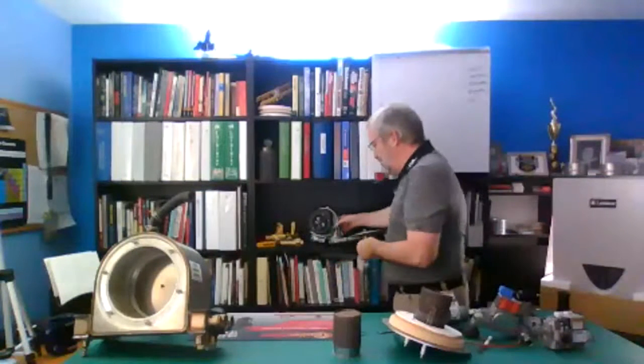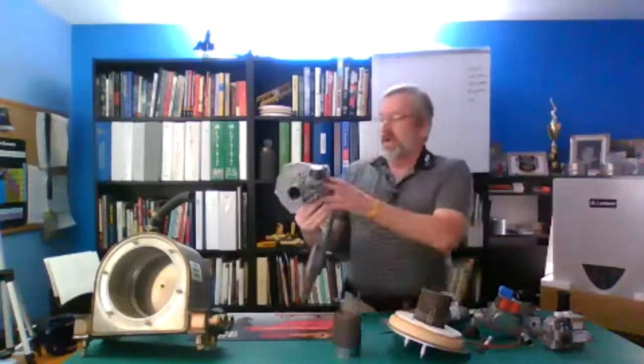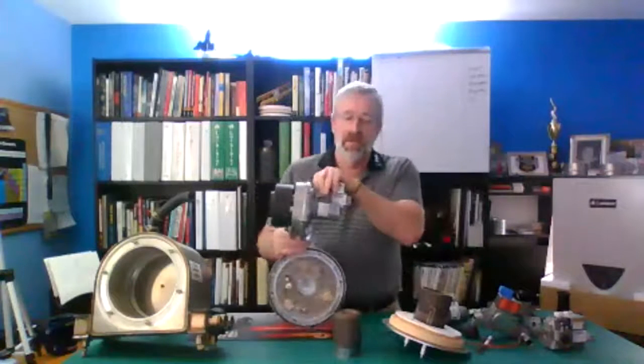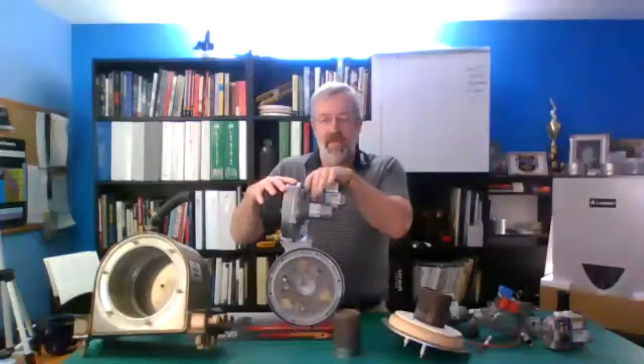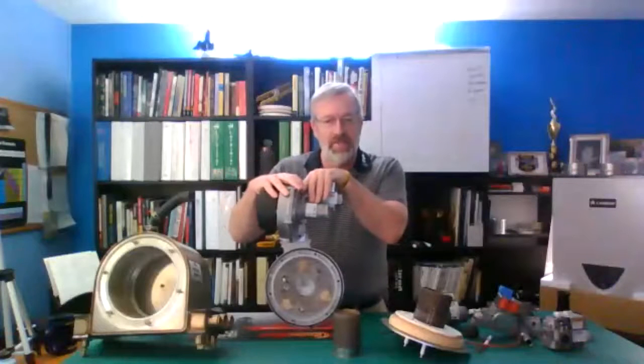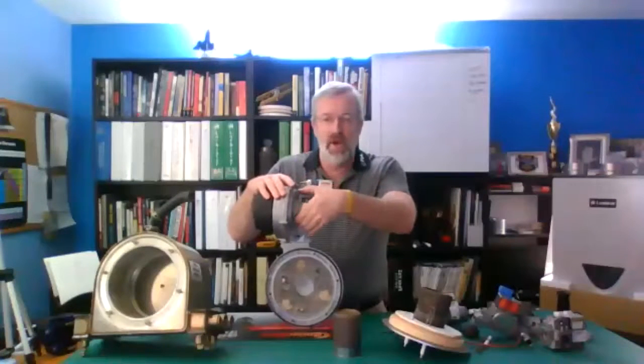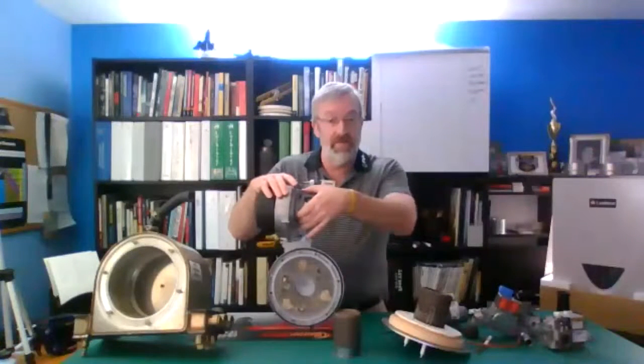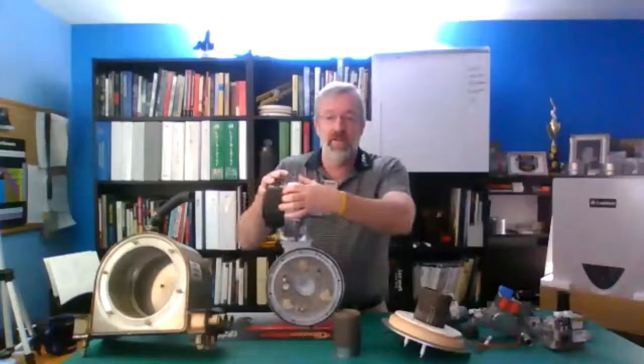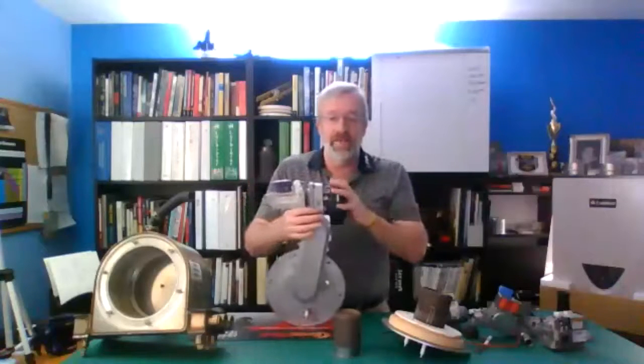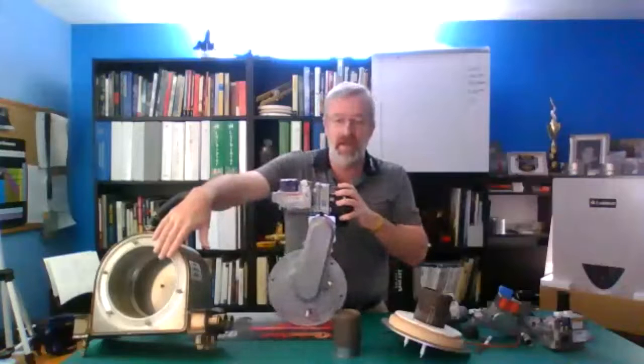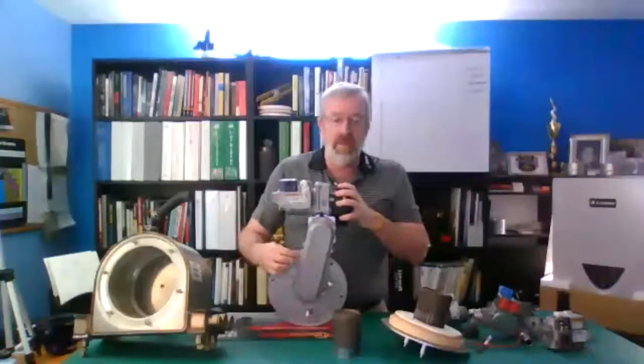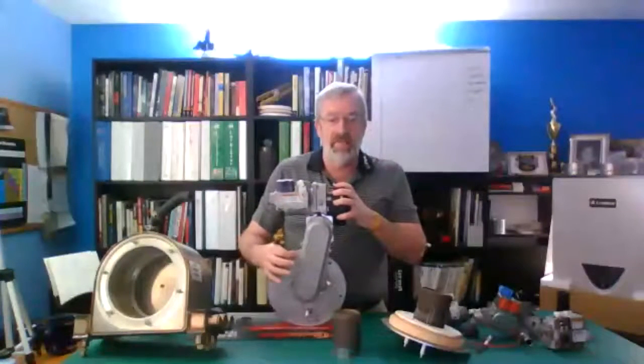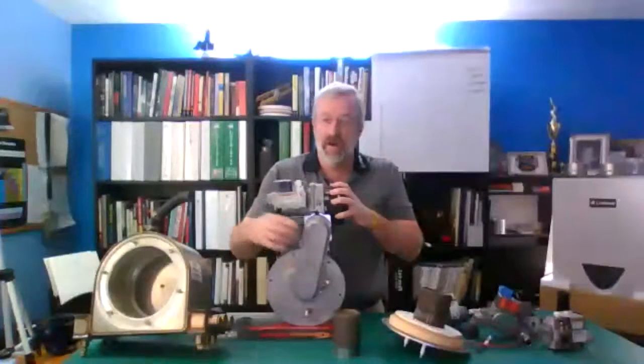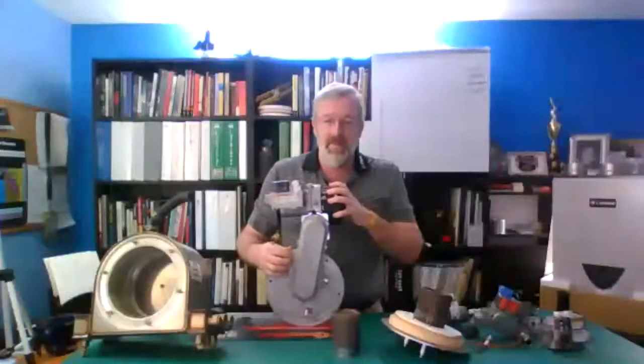And I'm going to move to remove my fan and burner plate assembly. So in this case here, I still have the gas valve on it, just more as a demonstration purpose. So I would take this off. I'm going to disconnect my gas train from my fan. Now as I'm looking at the front of it, matches up to here. It's 10mm nuts on these studs, and it's the same on fire tube or water tube, 10mm. I'm going to take them off.